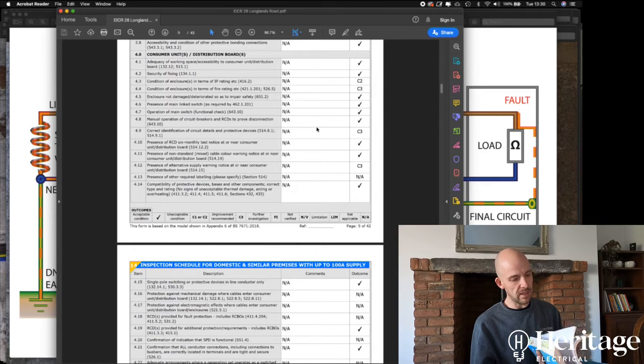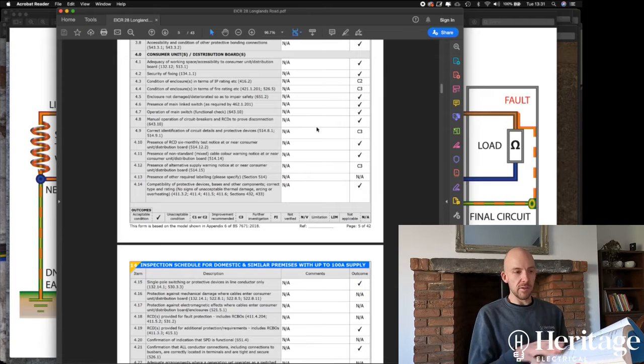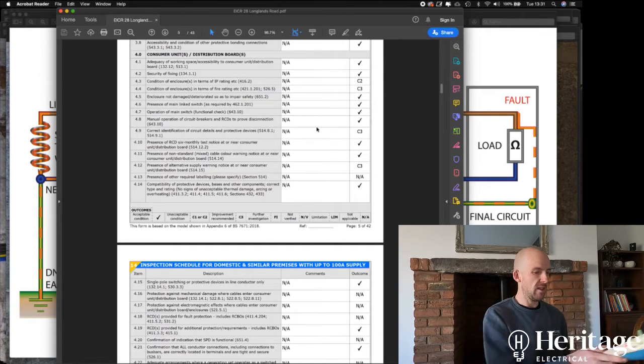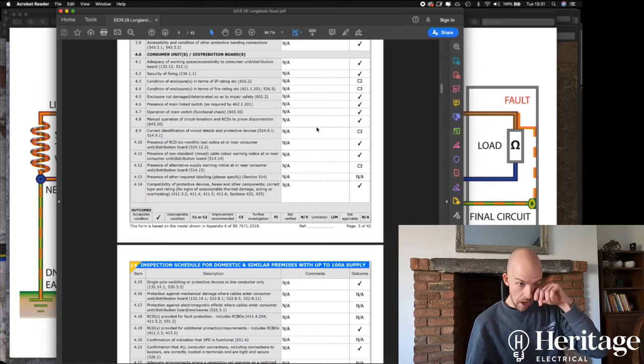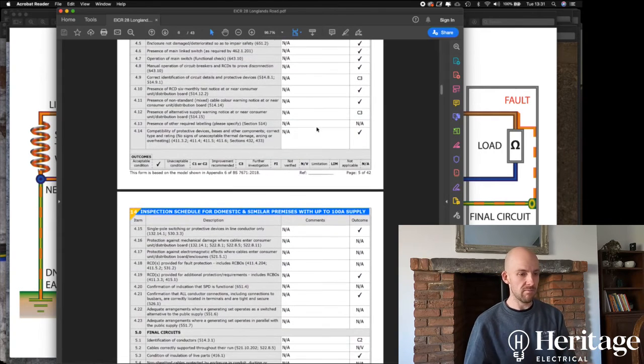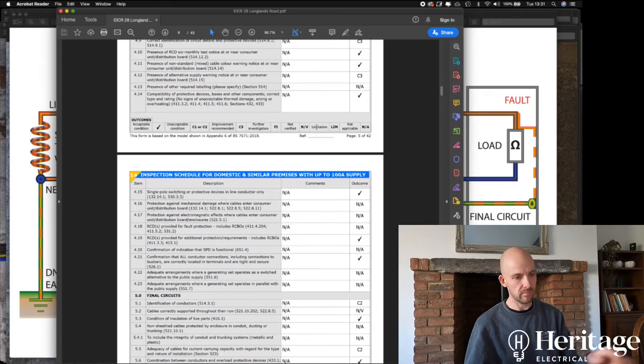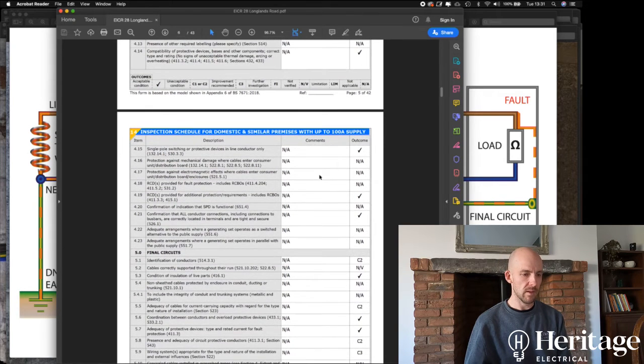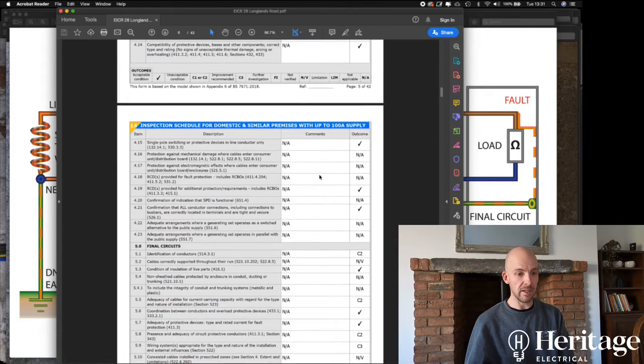We've got a regulation number there. So this is under isolation and switching. A main linked switch or linked circuit breaker should be provided as near as practicable to the origin of every installation as a means of switching the supply on load, which means with current flowing in the installation, and as a means of isolation. So it is a requirement there. It's referenced on here, and so you see that every inspection that we carried out has got a relevant regulation. Following those regulations means that the installation adheres to legislation.